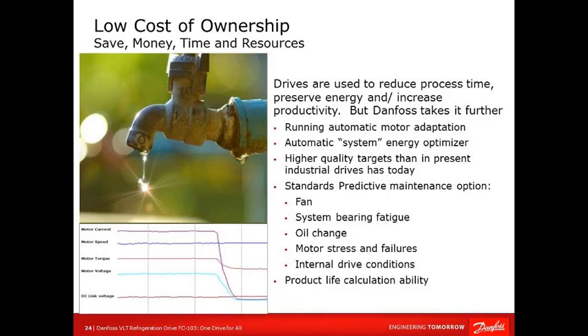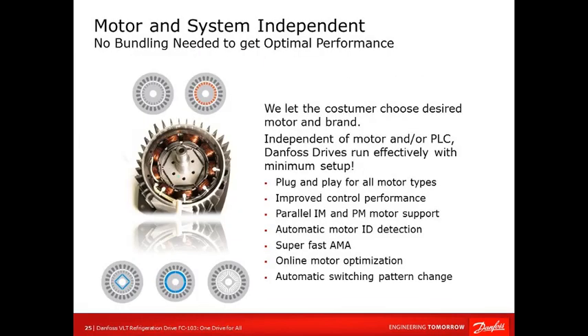There are a lot of requests for that, where we could simulate or provide a warning, or if it's on a PLC, a warning, saying hey, check out this motor, there could be something going on. So the idea is the drive could use the intelligence that's in there, and you'll learn that the capability of these drives now ranges from PLC control to even more exotic, where we can do servo type control just in a VFD. So the drives are getting more and more intelligent, and that's the expectation moving forward, that you're going to have less and less people on site, and you're going to need something to alert that, hey, maybe come check this out.